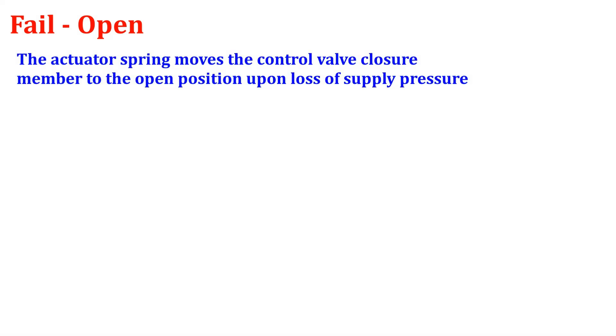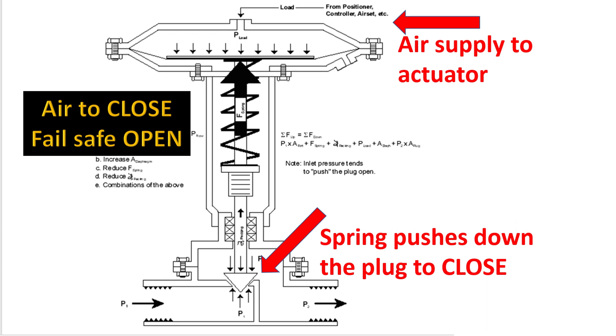First, let's see what is basically failsafe open. In this failsafe mode, the actuator spring moves the control valve closure member to the open position upon loss of supply pressure. You can see here this is the actuator assembly, and we are supplying air at the top of the actuator since it is a direct acting actuator. The main principle of an actuator is the force balance between the actuator spring and the diaphragm.